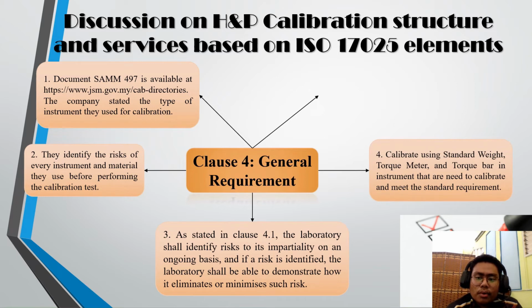So the fourth point is more on the services that are provided by this company. This service is more on the force scope. It mentioned that they calibrate using standard weight, torque meter and torque bar on the instruments that need to be calibrated and meet the standard requirement. So the standard weight, torque meter and torque bar are the instruments that they use to calibrate the force instrument.